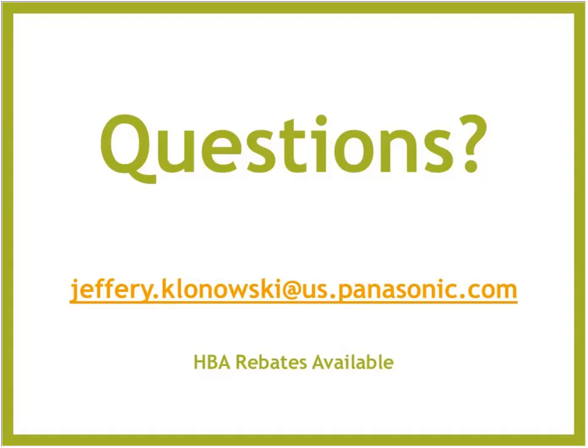And like I said, I was looking at HRVs and ERVs because we've had some houses that have had those installed and have found that the efficacy on some manufacturers is not listed anywhere, and I've only found one so far that had an efficacy of 4. So we're going to be looking for that, so make sure that it's on your literature, I guess. And Panasonic is already ahead of that curve. So I'm speaking to the people that don't necessarily use that product to make sure that they have a listing, because if you're going a performance pathway and a guy like me is going to be involved, I have to see that verification on your paperwork, or have to be able to find it somewhere. If you're doing the prescriptive, then you need to provide that information to your local code official that's going to come in and do the inspection, because the efficacy is a mandatory requirement.